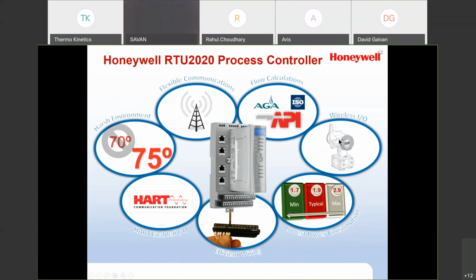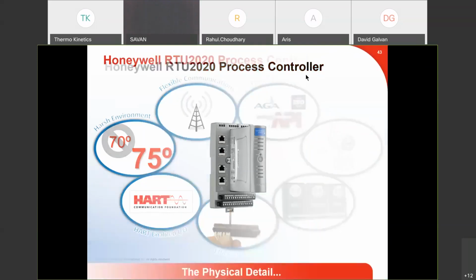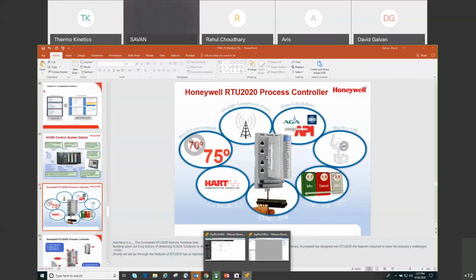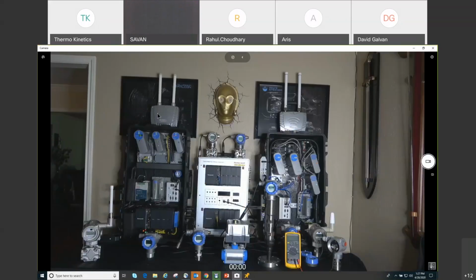So now what I can do is I can take an FDAP, a field device access point. Basically, it's this right here. Let me just show you what it looks like. I can take this field device access point, and I can connect it to the RTU. Here's the RTU. And I can bring in these wireless transmitters through the RTU. So I can have a combination of wired instruments connected to this, and I can have a wireless instrument, or up to 25 wireless instruments connected to this.